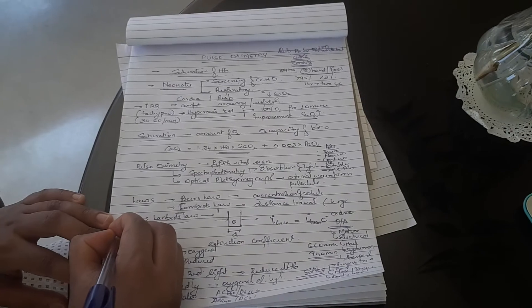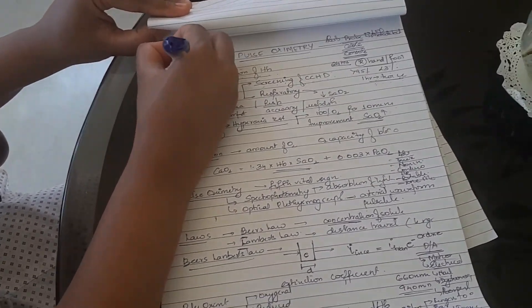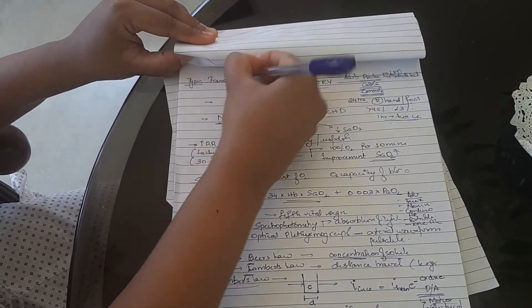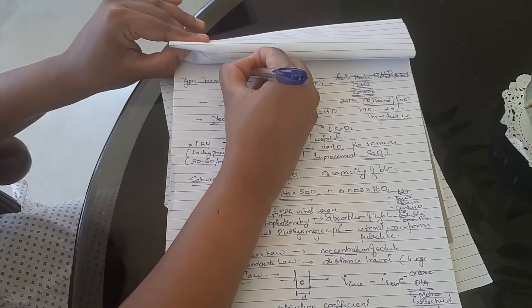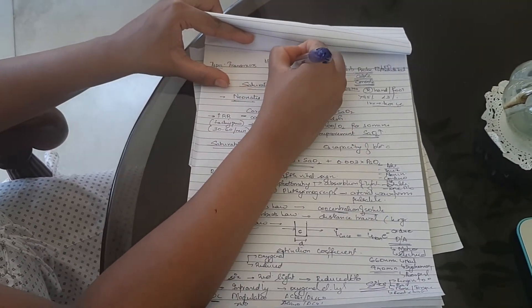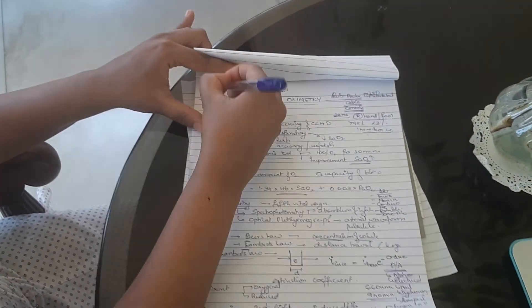Next, we move on to types. There is transmission type pulse oximetry where the incident light is detected. There's an LED here and the photodetector is on the opposite side. Like in a finger, the photodetector is on the opposite side. This is transmission type.